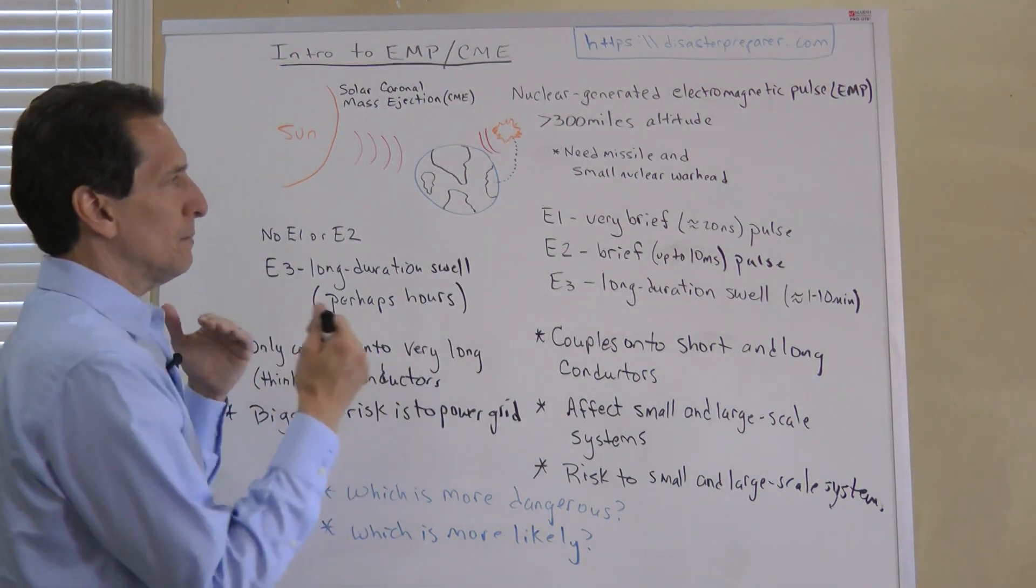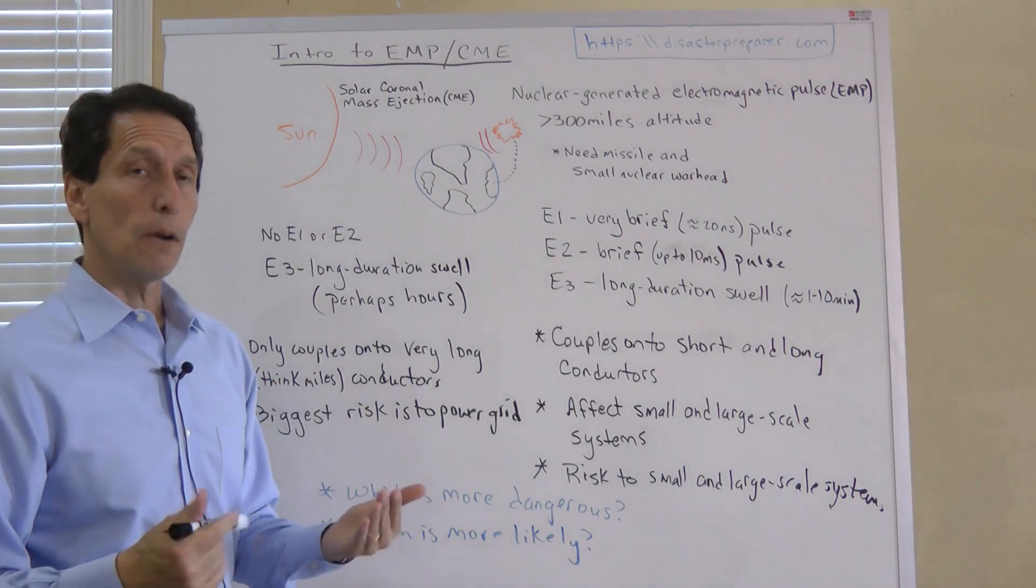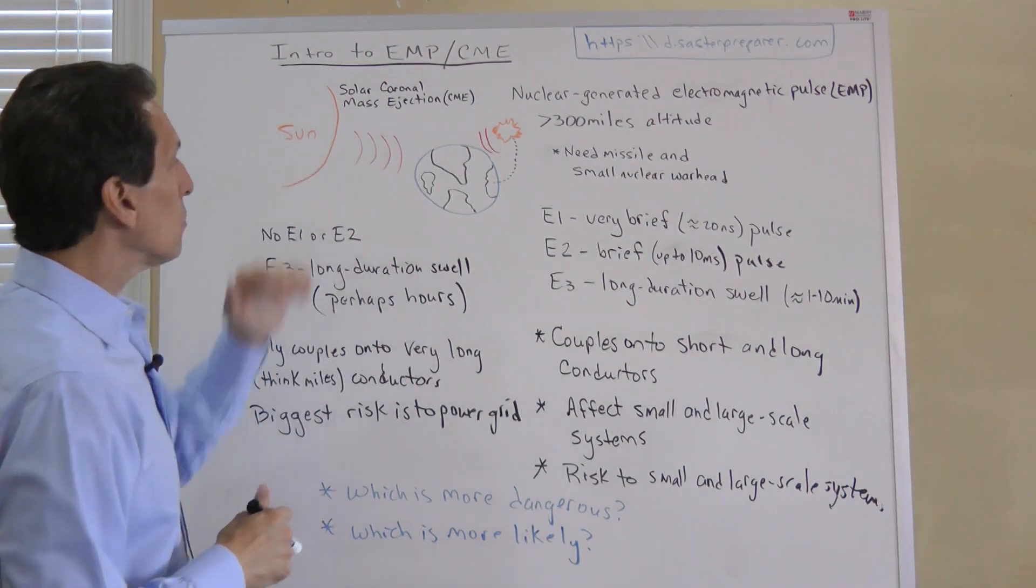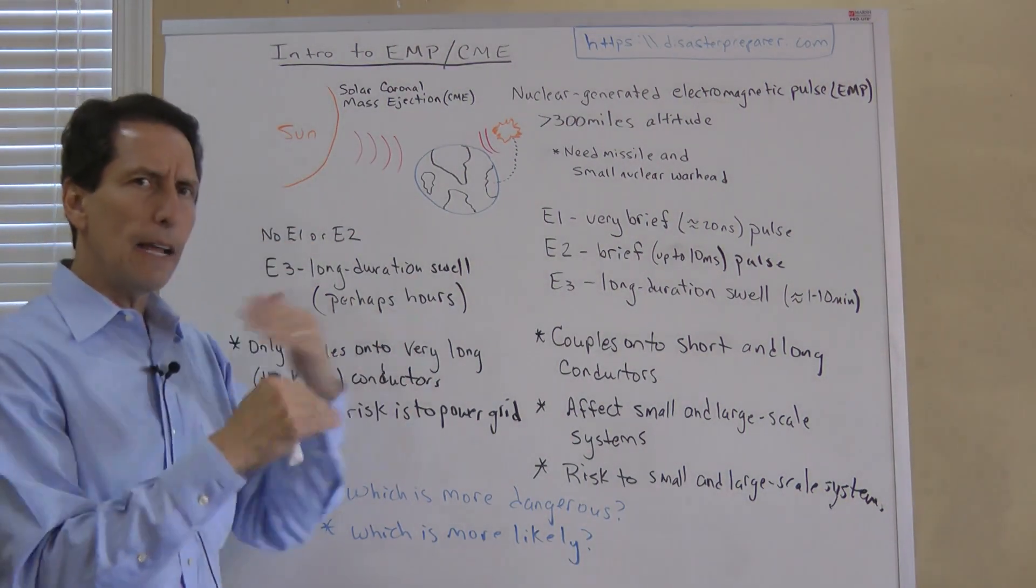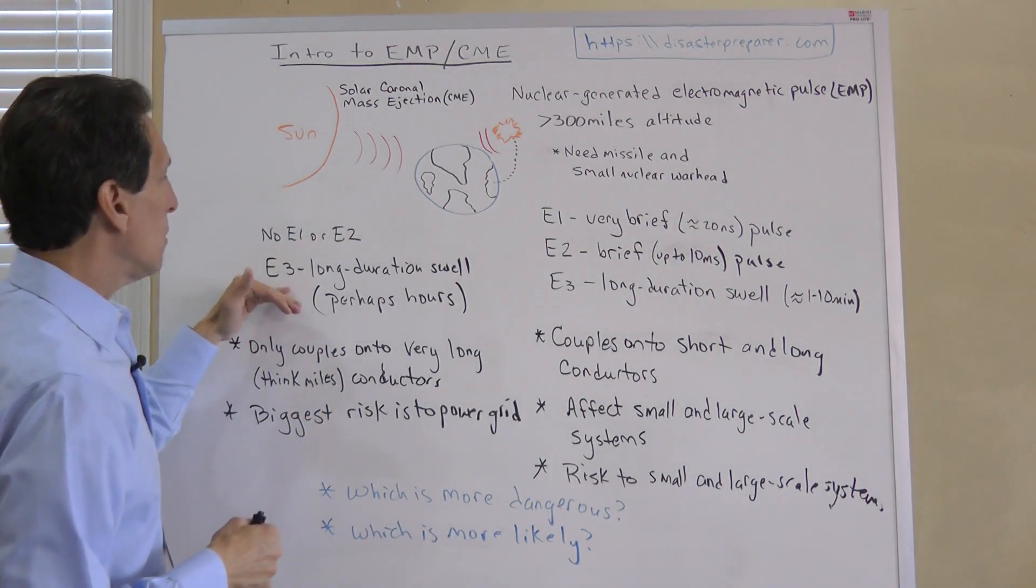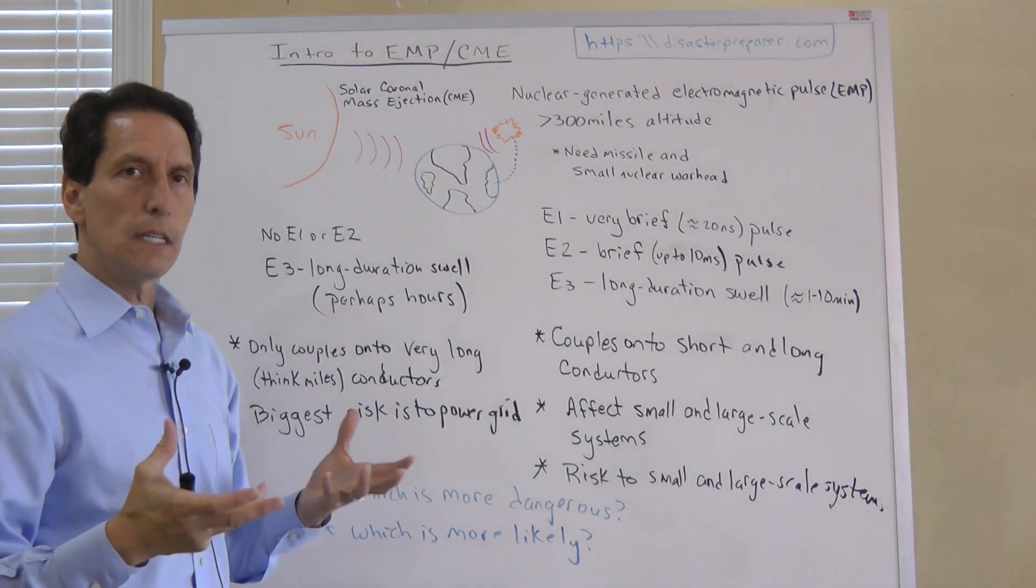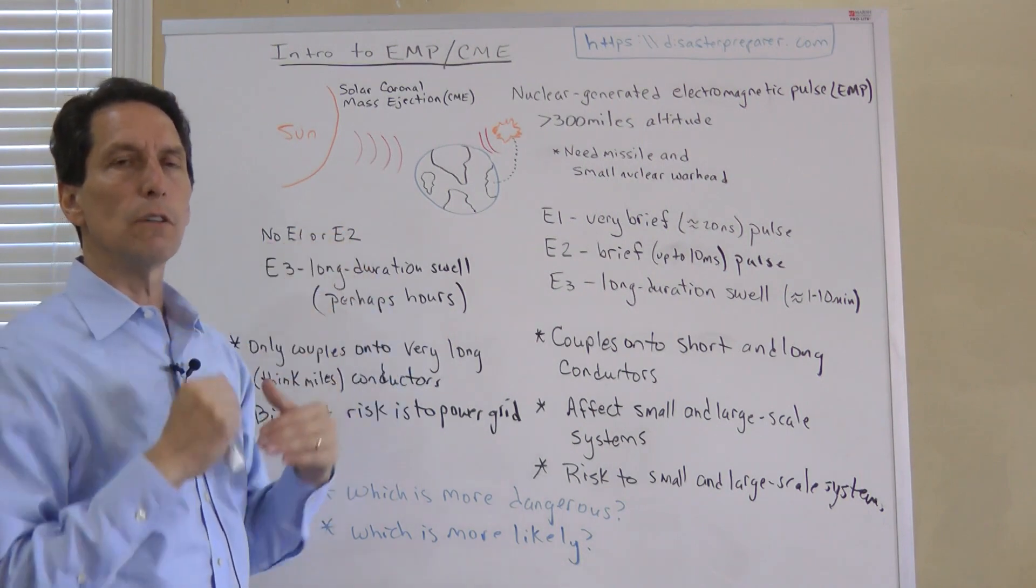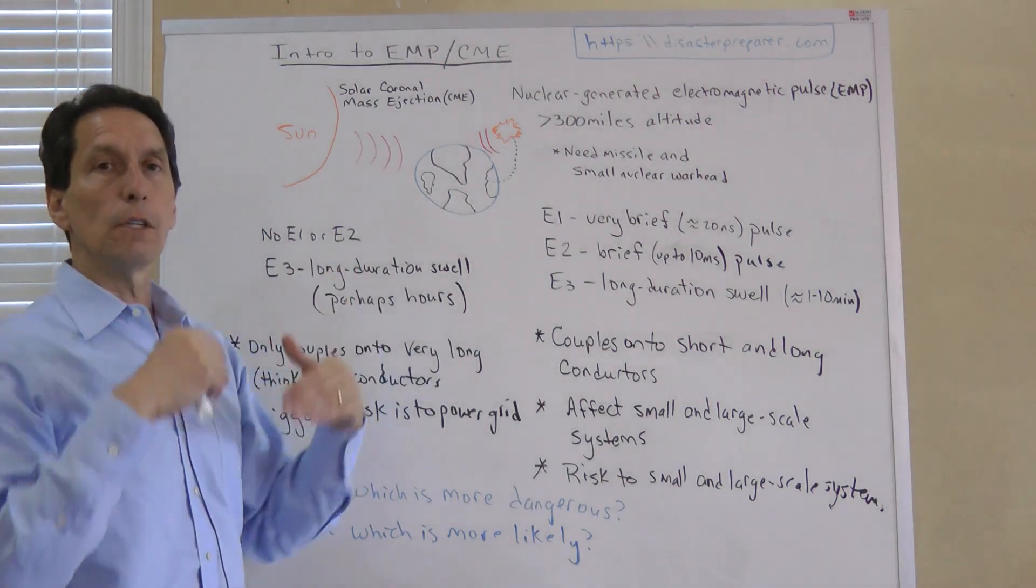Let's talk about the specific waveforms generated from these two things because it's really important to understand that they're different. A lot of times people think they're one and the same, but they're different. A solar CME doesn't have high frequency energy that perturbates the earth. It only has an E3, a long duration swelling effect on the energy in conductors. Think of that like a wave coming in and rising the voltage levels on those long conductors. It might take hours for that energy to fully rise. This is not quick, over in a millisecond—it's a slow energy build on very long conductors.